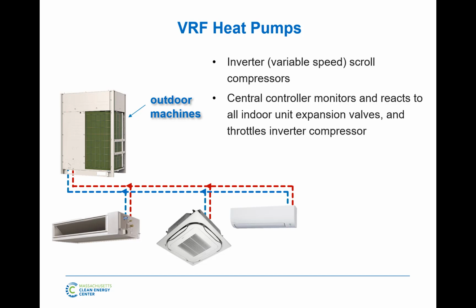These are all optimized. VRF manufacturers these days don't really care how good we do at full load. On your July 31st, 2 p.m., 95 degrees outside, at that point in time, which we call the full load or the peak design, which happens less than 1% of the time, they're pretty good, but that's not what they care about. They care about the 99% of the year that you operate at part load. So that's why you'll see later in the efficiency standards, the industry has followed and said, okay, well, we're going to judge you on how good you do at full load, called the EER, but we're going to make a real rating called the IEER that looks at how good do you do at 75% load, 50% load, 25% load. And so that's how we judge them, and that's what manufacturers really work towards is part load efficiency.